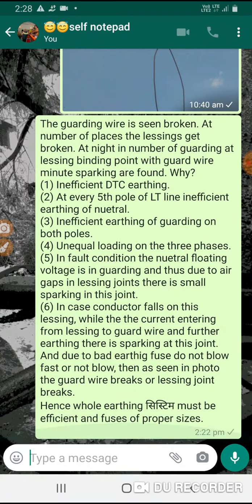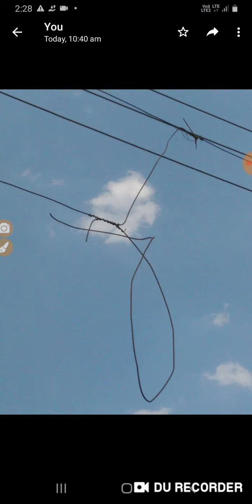And hence, to avoid this damage to the guard wire or lacing, the load on the transformer on the three phases shall be equal. That is, the balance current should be as near to zero as possible. The neutral earthing of a DTC shall be efficient. Every pole neutral earthing shall be efficient. Guard wire earthing at both poles shall be efficient. In short, a complete earthing system shall be efficient to protect this guarding.